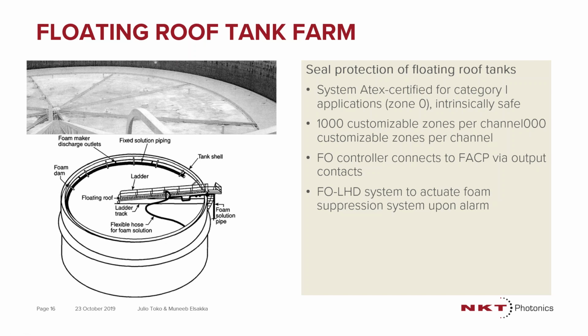And if you look at the advantage of fiber optic linear detection from a technical point of view, you can actually tell which side of the tank needs to be flooded. In the case of a tank farm, one advantage is you can already flood the other tank that's in proximity of a fire. So if two tanks are next to each other and one is on fire, you can literally deluge one area specifically and save money on foam, and also protect the other assets before anything happens. So you can already start dumping water to cool that other tank next to it. This is really an area where we see a lot of compatibility, and where you can use a different type of linear detection.